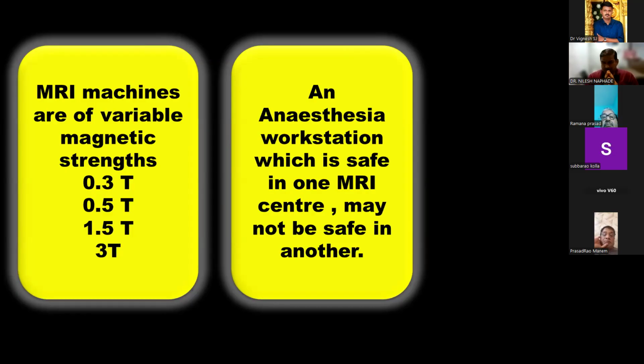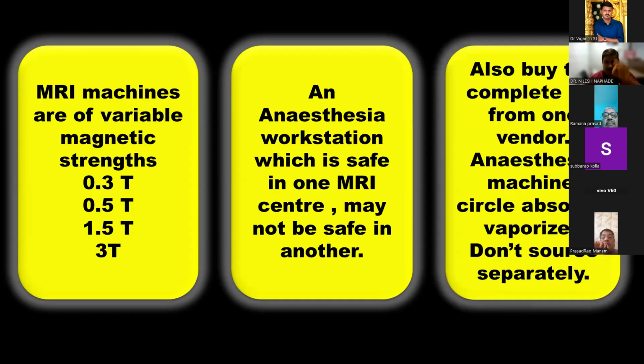So you need to be conscious. Discourage shifting of machines from one center to another, or from one operation room to an MRI room and all that. Or if at all that is done, ask somebody to take full responsibility for whether the anesthesia machine is compatible with the MRI machine that you are going to use it with. Also buy the complete set of the anesthesia workstation or Boyle's machine from one vendor. The anesthesia machine, the circle absorber, the vaporizer, everything related to the anesthesia machine should be bought from one vendor. Don't outsource. Don't buy a Boyle's machine from one vendor, a vaporizer from another vendor, a circle absorber from another vendor. Because when you buy the circle absorber, you might forget, or if somebody else buys it for you, you might forget to tell them that this circle absorber is going to be fitted on a Boyle's machine in the MRI center. So always buy it together and don't separate it. Put it together, keep it together. Otherwise, missile effect and dangerous projectiles can develop in your MRI center.